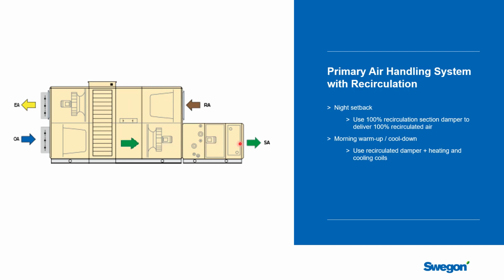Deliver it out to the space, and then whatever beams are in the zone that's either too hot or too cold, with some air flowing through them, you can now start to do some local heating and cooling in that space with the coils that are built into the chilled beam. So a nice thing to be able to do if you want to have either night setback or morning warm up or cool down as an option.